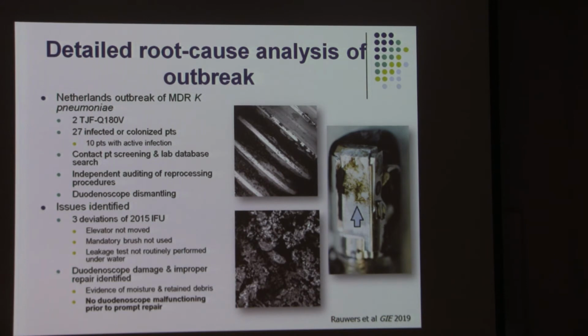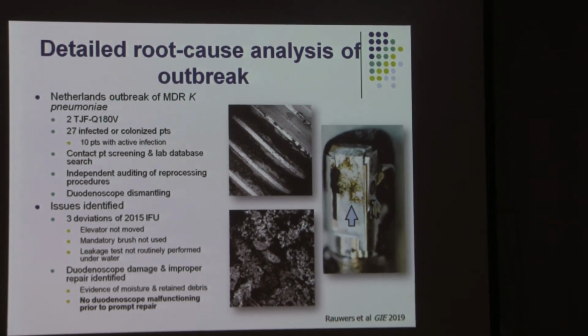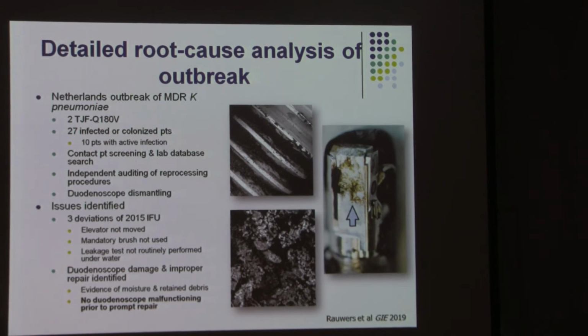They invited an independent auditor who was involved in the first outbreak to evaluate their reprocessing procedures, and they did duodenoscope dismantling and identified 3 issues. There were 3 deviations at that time in 2015 from the instructions for use. The elevator was not moved. The mandatory brush, even though required, was not used, and leakage testing was not routinely performed underwater. The other thing you've seen in previous outbreaks is that there was evidence of moisture and retained debris, and at that time the duodenoscopes were functioning without any problems that would have prompted a repair.